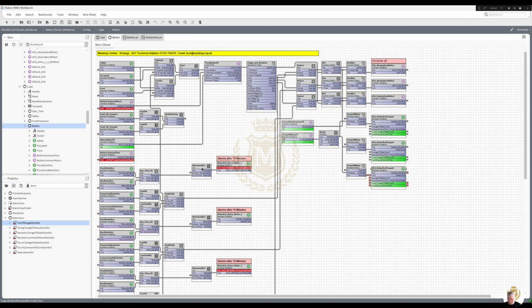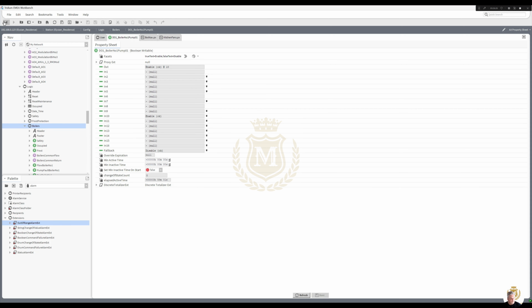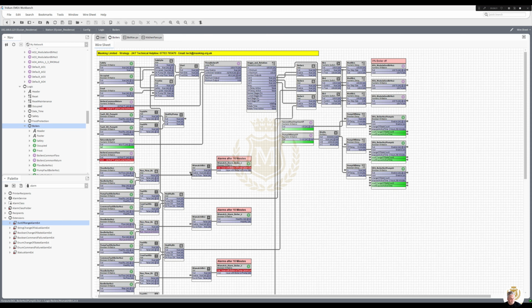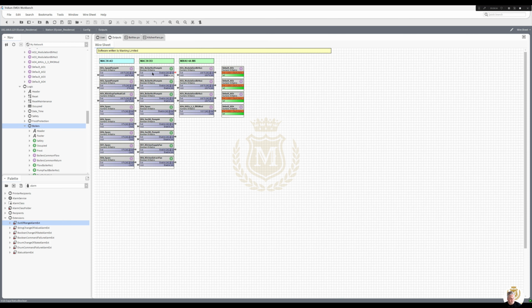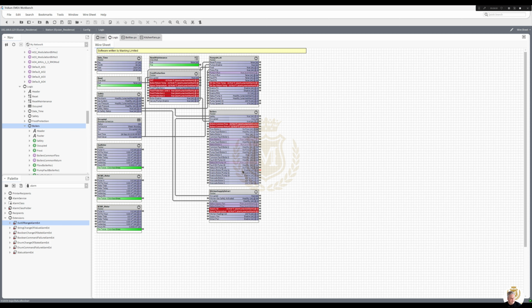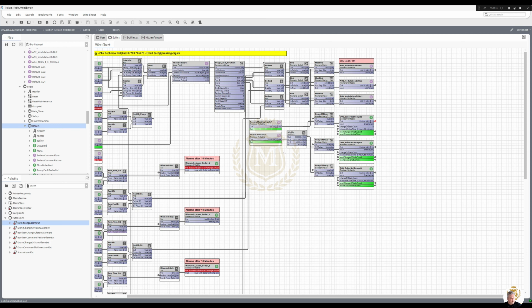Mismatch alarms, exactly what you saw before. So we're checking the enable. Now we're actually not checking the enable here, we're checking the enable on the physical output of the station. So if I double click that nib, you can see what I'm checking. In case I go in there and I override that, which is the last thing to do, which energizes the relay, where if I take it from this point here and I enable it, this isn't going to see me enabling it. Where if I take it from the very last point, then that shows that I've enabled it.